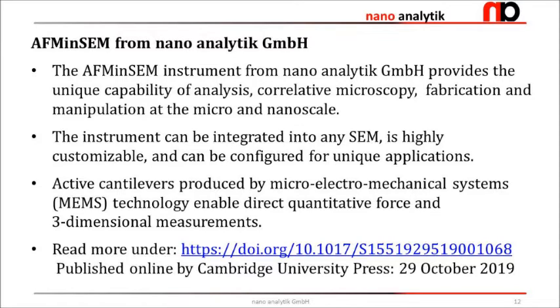As you have seen, the AFMinSEM instrument developed by Nano Analytik provides a unique capability of analysis, correlative microscopy, fabrication, and manipulation at the micron and nanoscale. The instrument can be integrated into any SEM system, is highly customizable, and can be configured for unique applications. The active cantilever produced by the microelectromechanical systems technology enables direct, quantitative force and three-dimensional measurements.